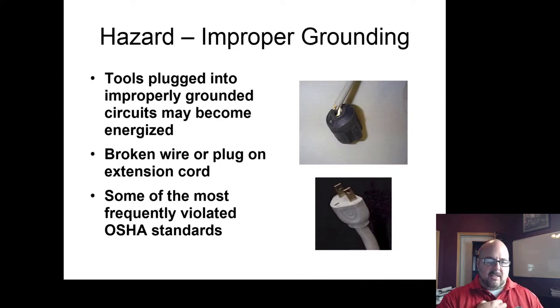So in this slide, Todd's showing two possibilities in which there may be improper grounding. The top one, what I see is a strain relief that's damaged, and it looks like there's no clear copper wire. That's usually the ground. And then on the bottom, you see somebody has physically removed the ground prong.